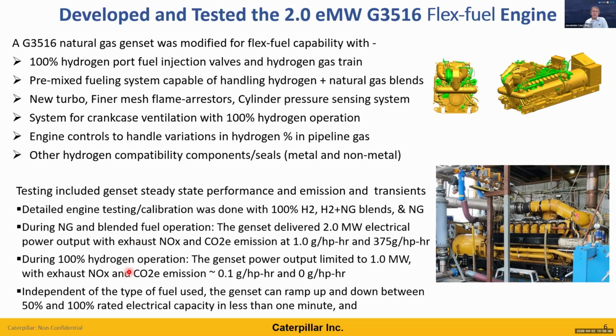But during the 100% hydrogen operation, the same genset produced, we ran it up to about 1.3 megawatt, but because of the abnormal combustion that we saw in one or two cylinders, we limited the power output to about 1 megawatt. So on 100% hydrogen, that genset would run at a max of 1 megawatt electrical power output. But this is our first gen of that hydrogen genset. Our second gen is already pretty improved and can run much higher power output than 1 megawatt.